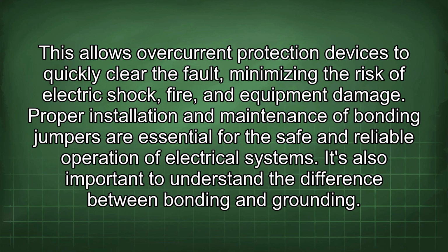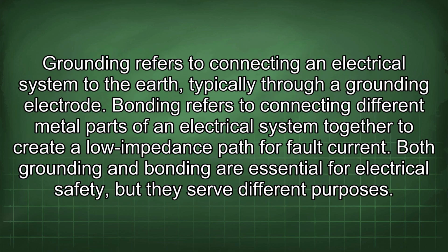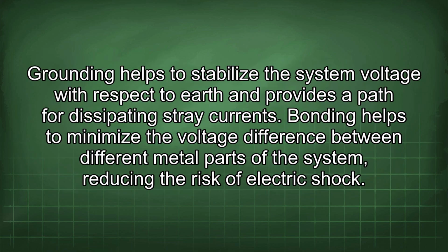It's also important to understand the difference between bonding and grounding. Grounding refers to connecting an electrical system to the earth, typically through a grounding electrode. Bonding refers to connecting different metal parts of an electrical system together to create a low impedance path for fault current. Both grounding and bonding are essential for electrical safety, but they serve different purposes. Grounding helps to stabilize the system voltage with respect to earth and provides a path for dissipating stray currents. Bonding helps to minimize the voltage difference between different metal parts of the system, reducing the risk of electric shock.